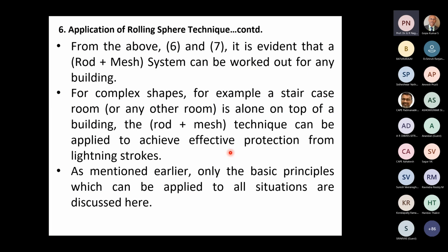We have been discussing, and from the above 6 and 7, it is evident that a rod plus mesh system can be worked out for any building of any complex shape. For complex shapes, as I have shown here, for example, a staircase room projecting on top of the top surface, or any other small projection, a room there on top housing electrical machines or whatever, then additionally the top surface of the projection must be provided with a necessary number of rods. Maybe a single rod may be enough, because remember it's already on top of a flat surface. Therefore, the critical angle, the geometric method can be applied relatively easily. Not always, but most of the time, because these projections are relatively small in area, the geometric method can be applied. If that is also very big, then of course we have to think of the rolling sphere technique, but that's a very, very unusual case.